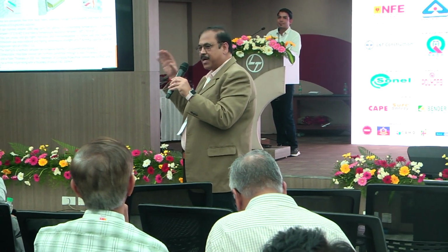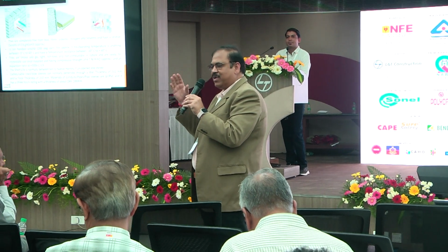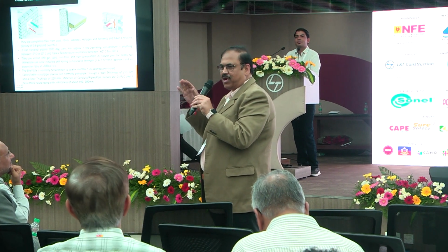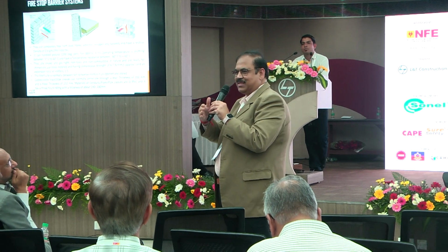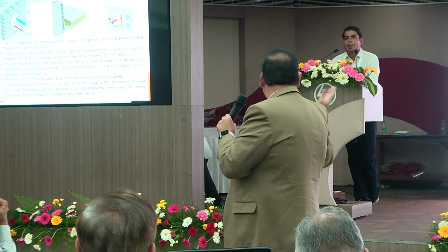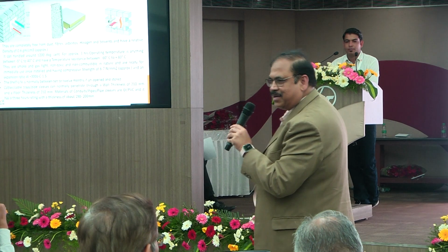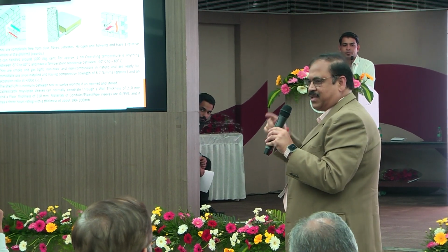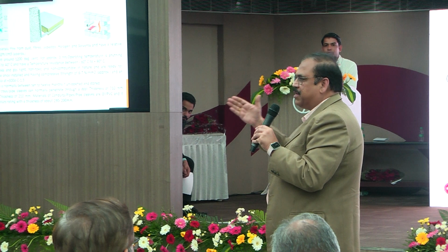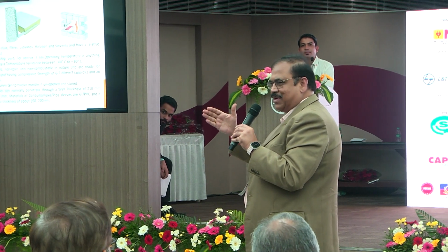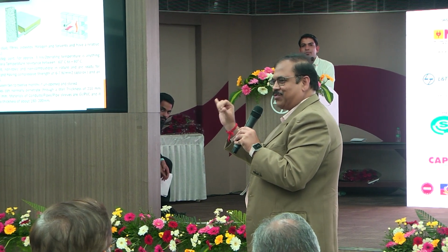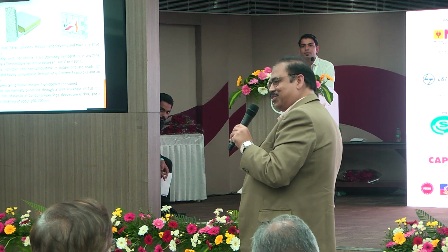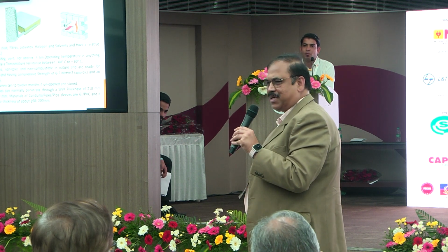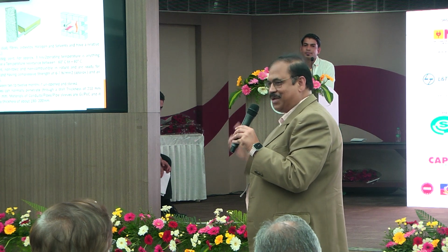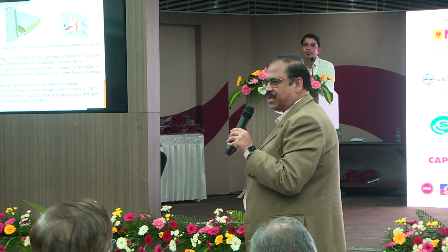See what happens there, as there was some topic of compartmentalization. Some compartments will be 4 hours, some might be 2 hours, like that. In a building, this looks like a 4 hours rated thing, but your FRLS cable cannot give that rating. When it is penetrating a 4-hour rated wall, it also should withstand 4 hours for that length. That is why these coatings are done in different compartments. Yes, sir, I think that is the key.